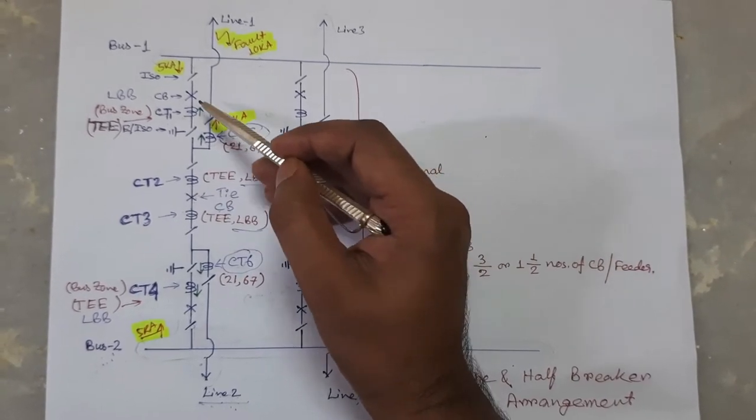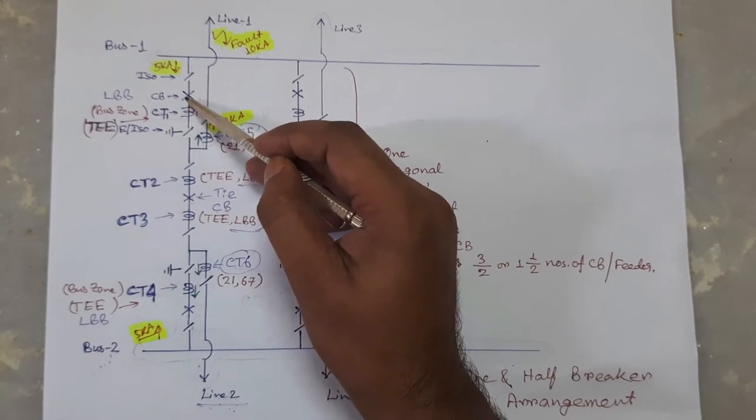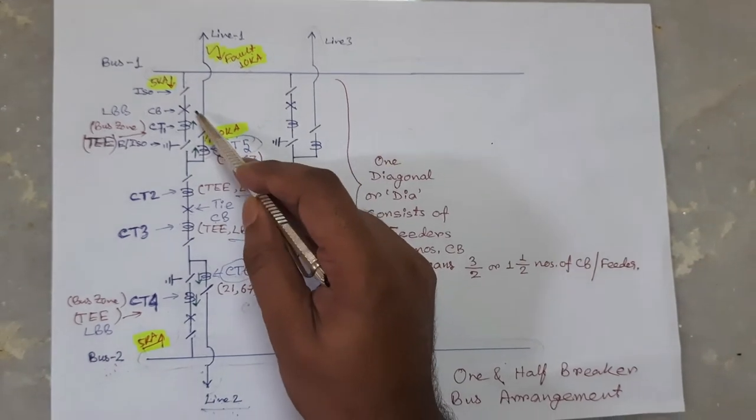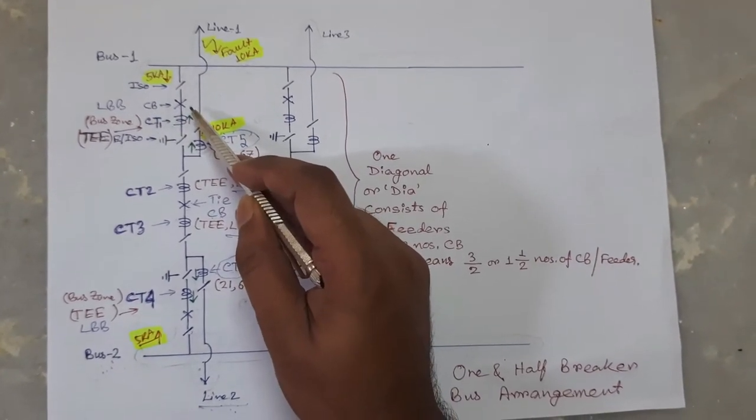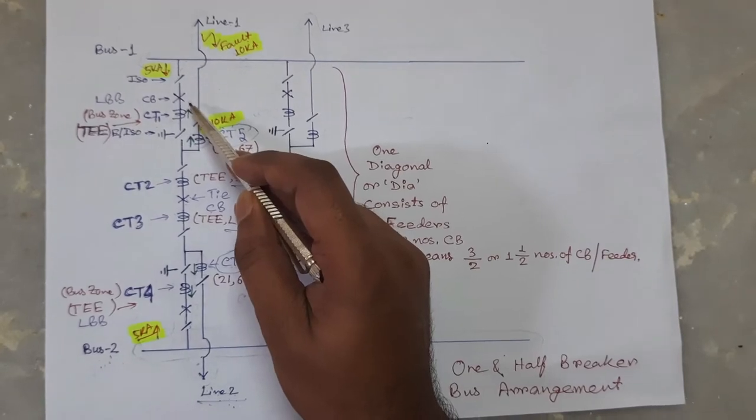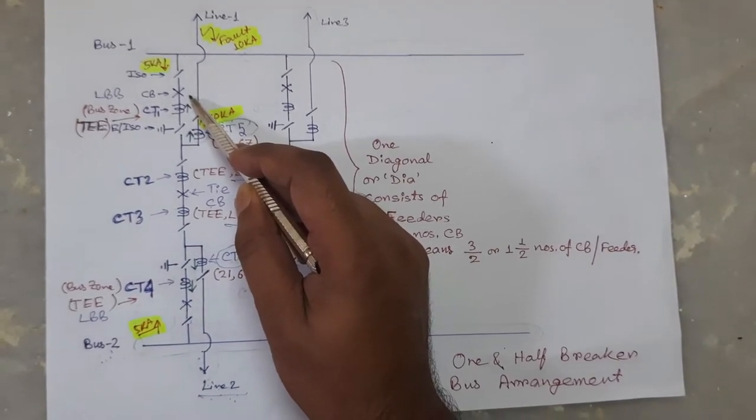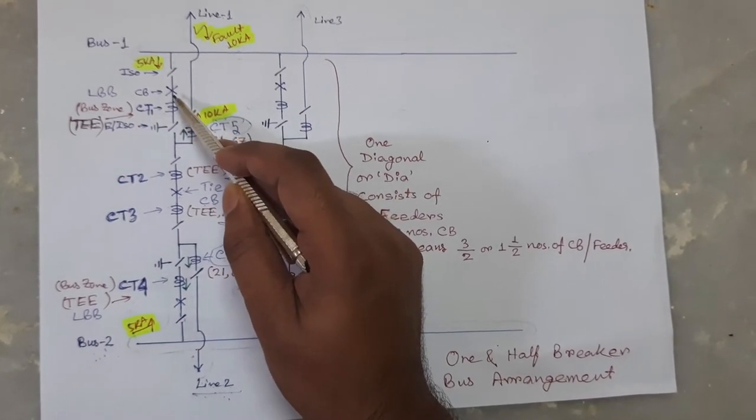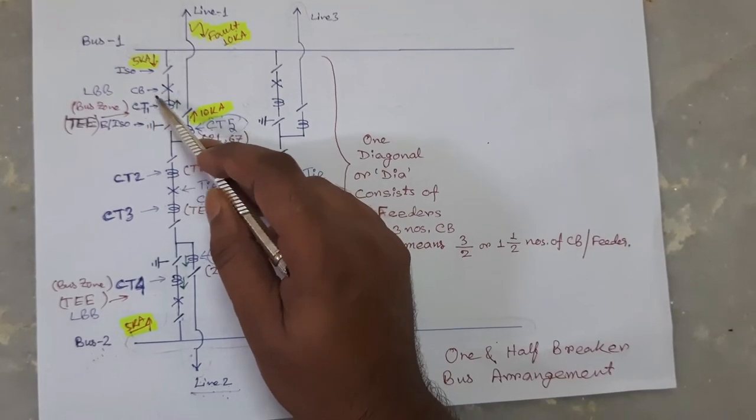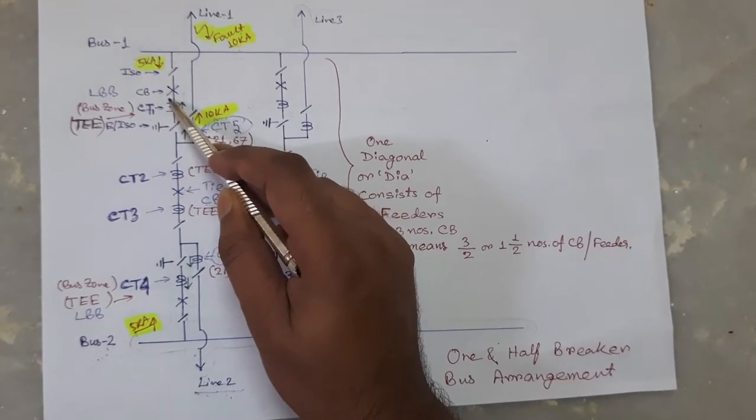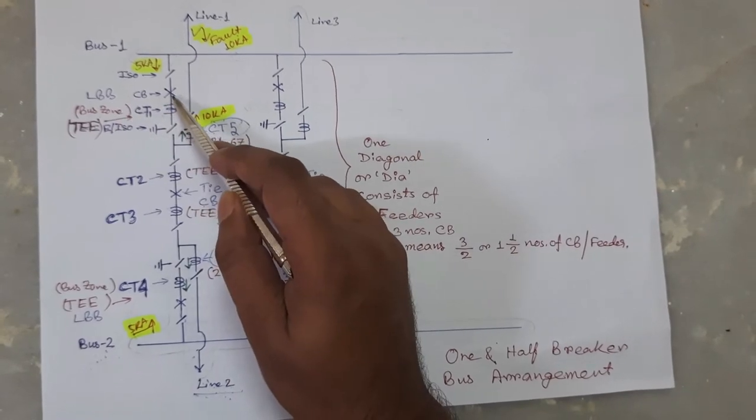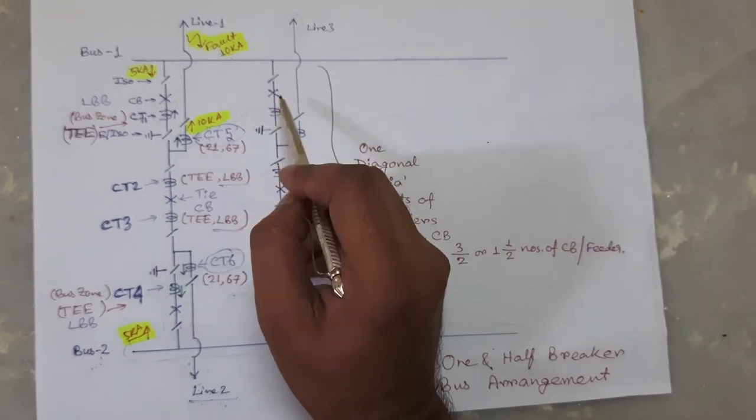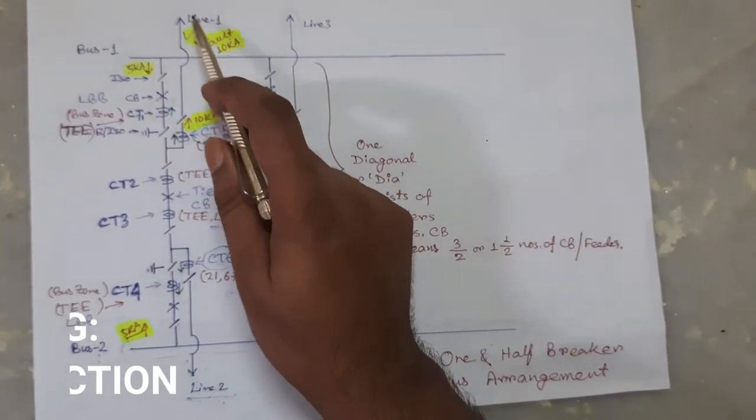distance protection also initiates main LBB protection as well as tie LBB protection. After initiation of main LBB protection, it starts its timer and waits for a predefined time delay, say 200 millisecond, with a hope that circuit breaker will successfully clear that fault. But if the circuit breaker fails to clear the fault, then LBB protection will operate and it will trip all other circuit breakers which are sourced to the uncleared fault.